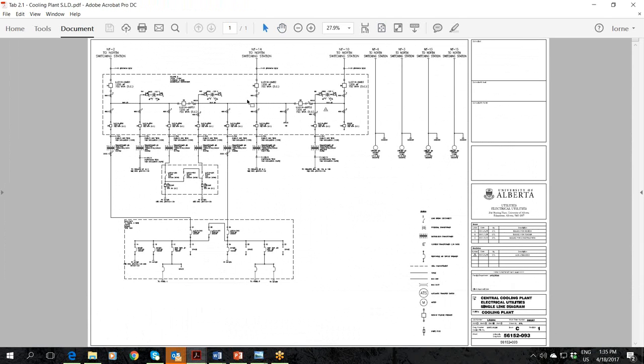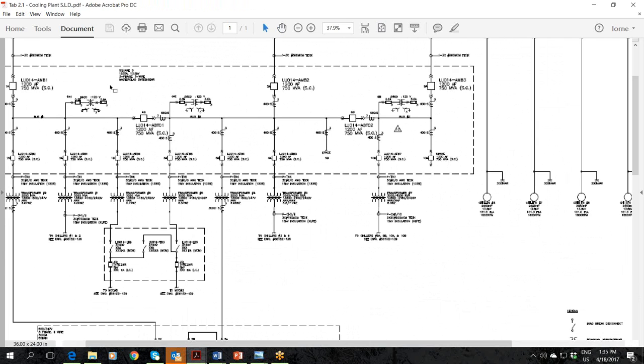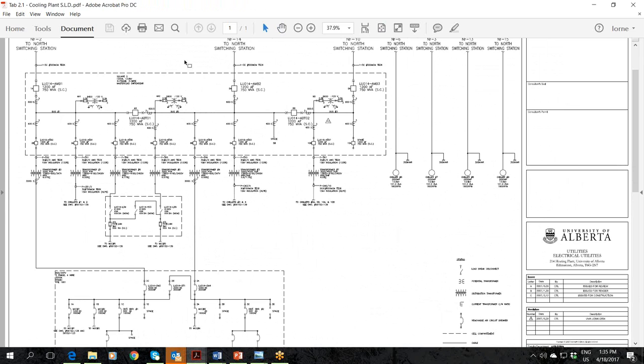Moving past that, talk a little bit about the original cooling plant. Was built in the 60s and 70s. So the architecture is very similar again. This one's 3 breakers, 1 from each of the 3 buses at the north switching station, again with main-tie-main configuration. Again, with remote protection and control cabinet, with remote electrically operating capability from both an HMI touchscreen as well as our DCS system.